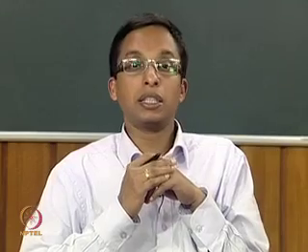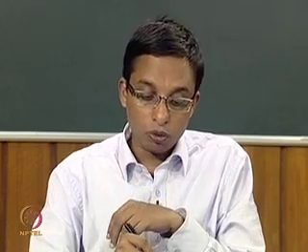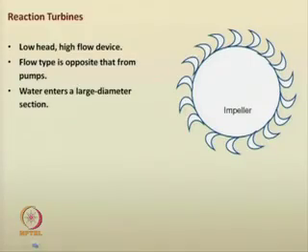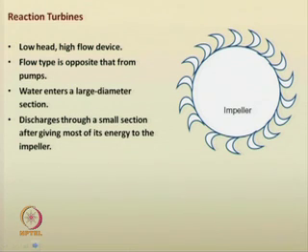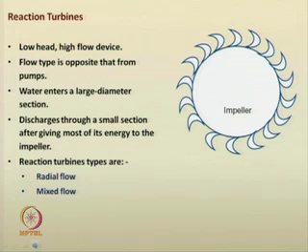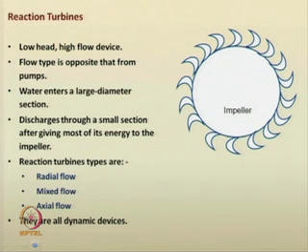Reaction turbines are opposite to dynamic pumps. Water enters through a large diameter section, then converges to a small eye, discharging through the small section after giving most of its energy to the impeller. Reaction turbines include radial flow turbines, mixed flow turbines, and axial flow turbines — all are dynamic devices.